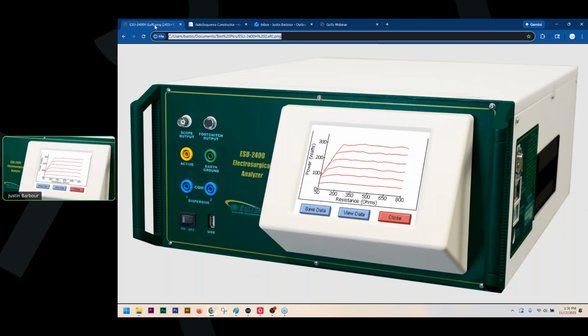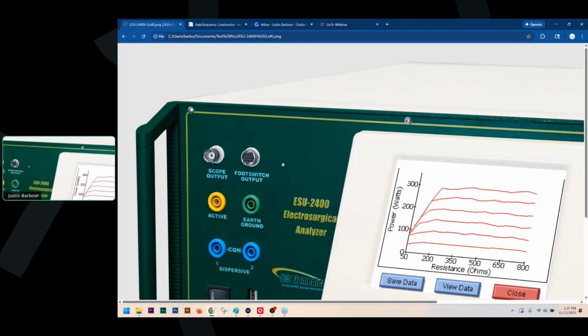And here's the other thing about our ESU analyzers - I want you to take a look right up here. This little multifunction port right up here in the corner, that's a foot switch output, which means you hook it up to our analyzer, and through the power of automation, it will automatically activate it. It will analyze whether or not it's within the specs you've set, and it will give you a pass or fail condition, and then it will say proceed to the next step, to which you just click the blue button and go to step 2.